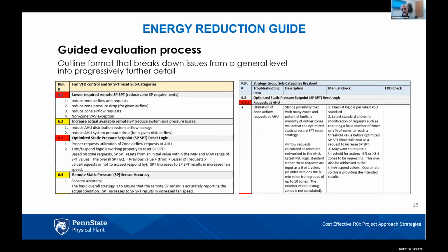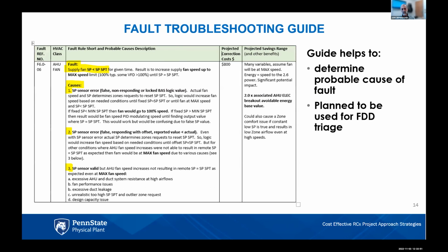Now that guide is for discovering faults, and this guide is for when you've discovered a fault: what are you going to do? It wants to determine the probable cause of that fault, and we're going to be using this in our FDD triage. Say we're using this in SkySpark and we have a fault that the supply fan static pressure sensor is reading less than our reset static pressure set point. The logic is going to drive that fan to full speed, and this could be occurring for some time. Naturally, that's a fault we want to discover. But when we find that fault, what are we going to do about it?